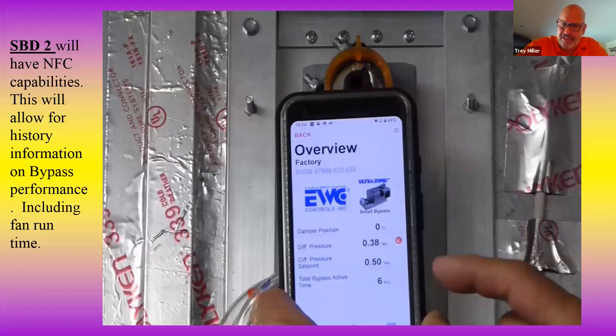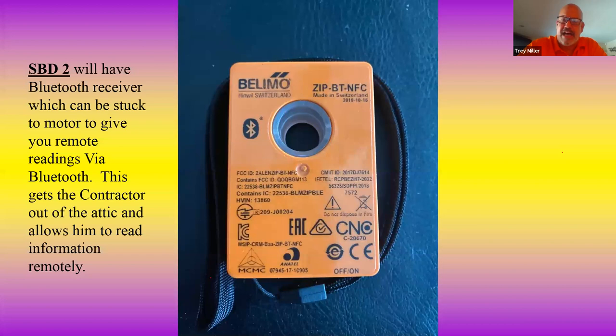Now, another thing that's neat is that we made it even easier because now we're going to have a module. The module is reusable. All you have to do is put it on any Belimo NFC motor. It will give you the information right through your Bluetooth. All you do is hook your Bluetooth up to the module, and then you can get out of the attic and go down in the house, and you can read all your information from the house. It makes it extremely nice. And then all you do is pull that module off, put it in your bag, take it to your next job, and stick it on the next motor and read it there.